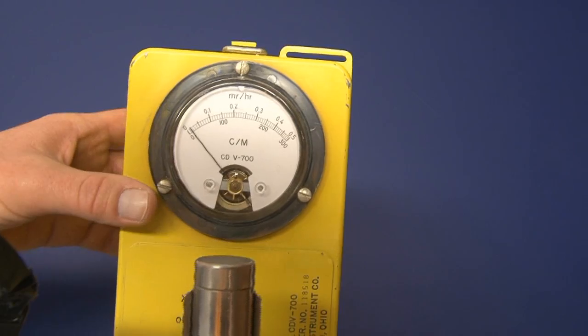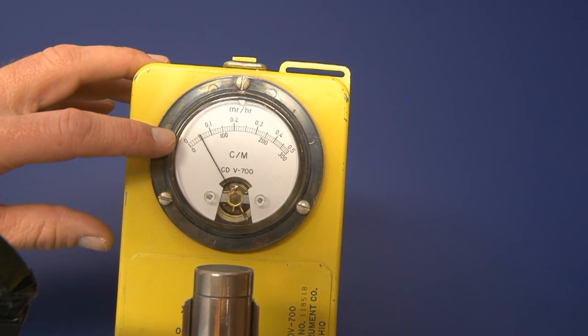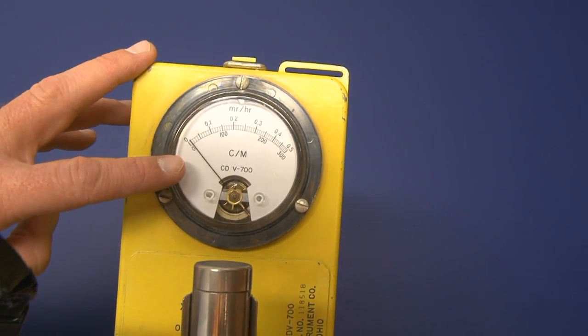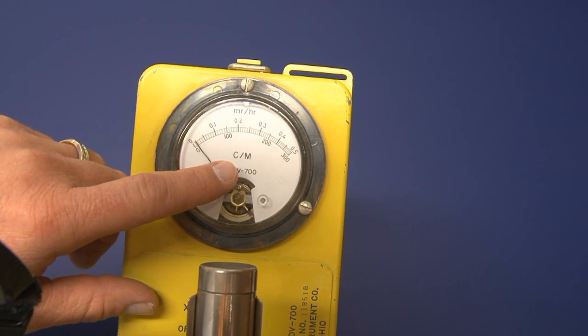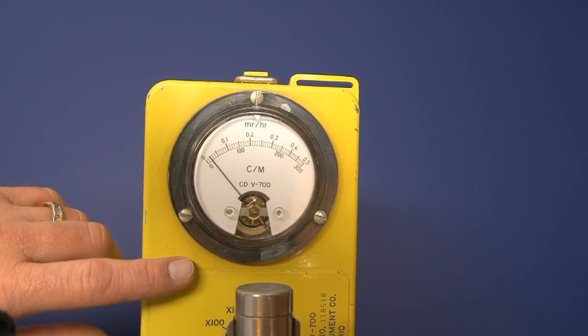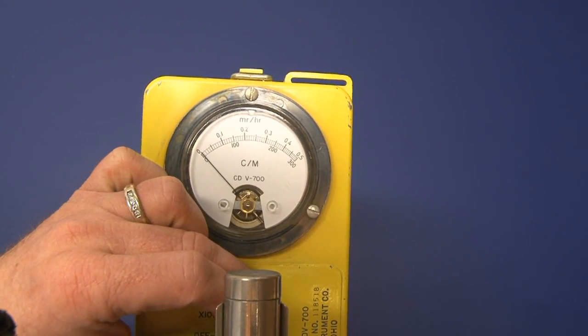How that works is, on the times 1 scale, it gives you an overall operating range of zero to 0.5 MR per hour, or from 0 to 300 counts per minute, depending on what it is you're surveying for, or how you've got your rotating rotary shield in either the open or the closed position.